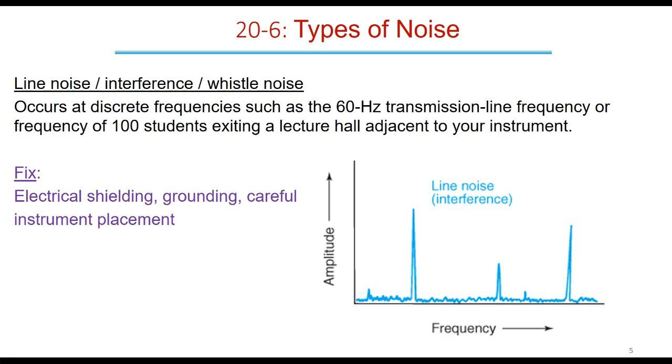So thinking about power sources, if you live in a place that's got kind of fluctuating power grid issues, you don't ever want to put all your instruments in one electrical bay. Again, you're overwhelming the system. It could cause some type of electrical issue. And then too many instruments adjacent to each other, they're literally going to start picking up each other's noise, because again, these are sensitive detectors. So we've got to be careful with our instrument placement.